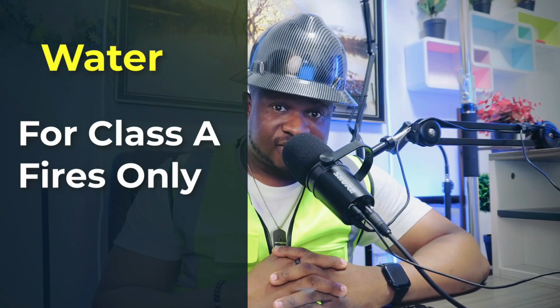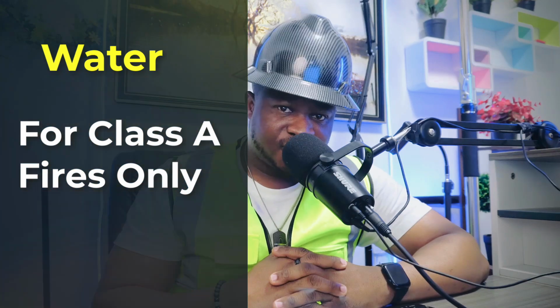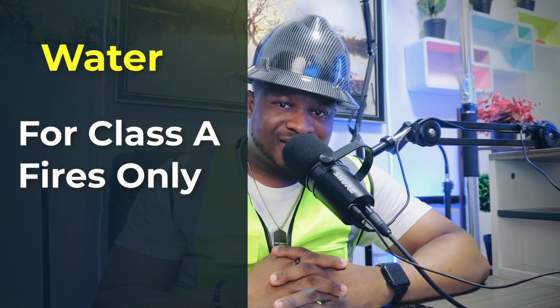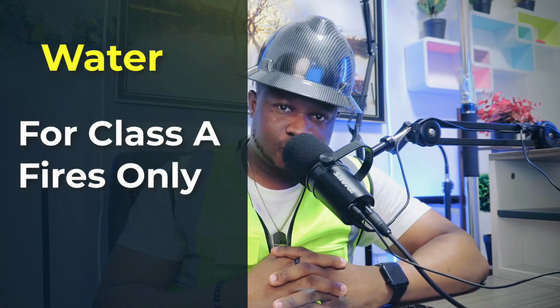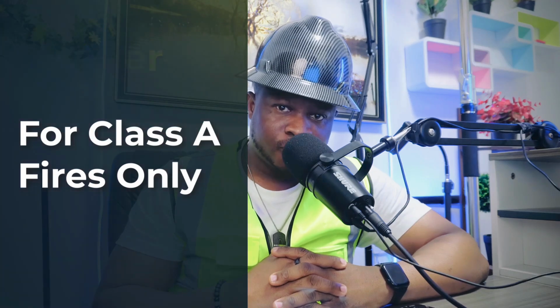Water is suitable for Class A fires only, that is fires involving ordinary combustibles. Water helps to cool the heat to a level that is below the auto-ignition temperature of the fuel. Remember, for any fuel to burn, temperature must increase to the point where the fuel can burn. That is the auto-ignition temperature of the fuel. So water helps reduce the temperature from reaching this point, thereby extinguishing the fire. This method is called cooling.